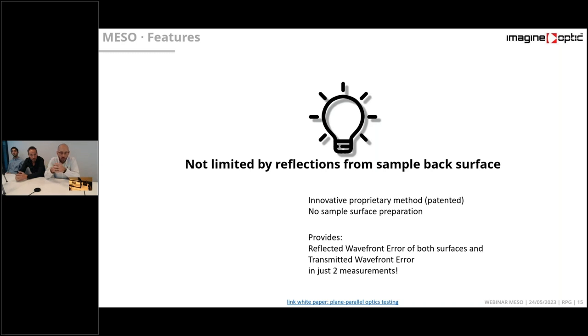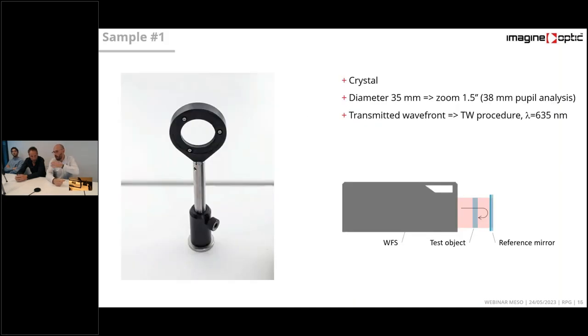Imagine Optic has been working during the last two years on the development of new procedure that we patented that allows you to take into account signal coming from the first surface and the back surface of a parallel sample, making the instrument very convenient for the characterization of plane-parallel optics without the need of complex or expensive add-ons. And we will showcase it.